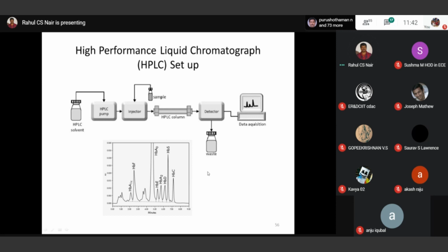Here in our institute, this is the setup. You can see the various pumps, and these pumps are very sophisticated. They can be very accurate also. You can pump even microliters per minute. Think of a pump that is pumping microliters per minute. These are that accurate. HPLC usually works in that range also. It's very accurate, and only then can you capture each component individually.